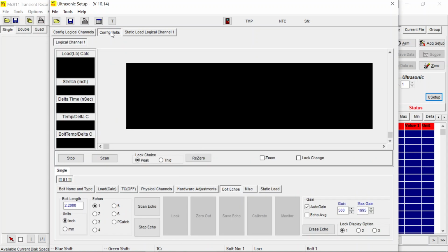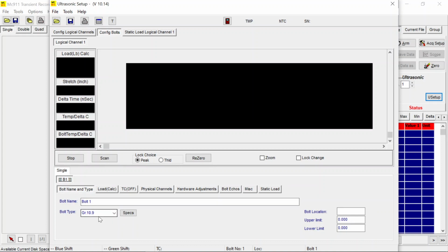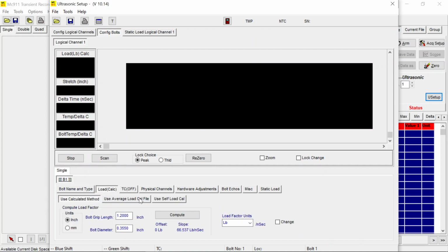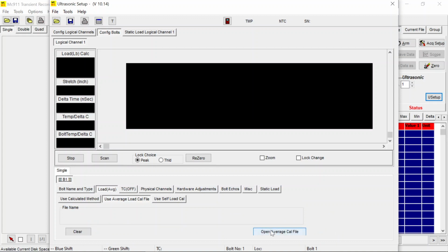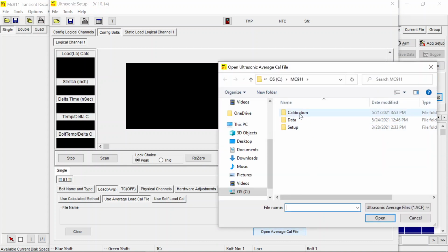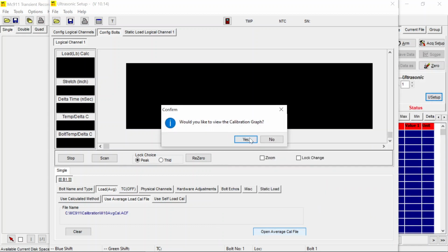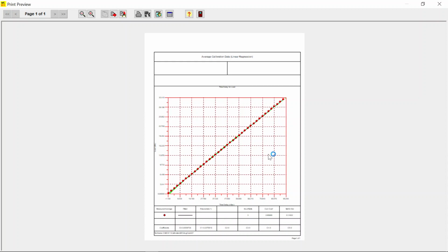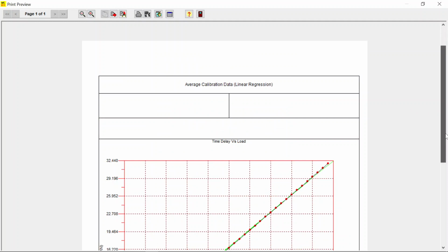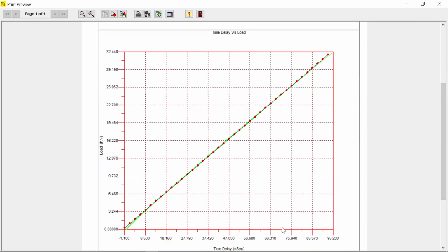So let's go into the config bolt. We have one bolt, 10.9, and our load is based on, let's use the average calibration load that we have generated before. In the previous video, you saw how we generated that calibration file, which was the M10 average cal file. So we're going to use this average calibration file for our load data. Our ultrasonic will be reading time delay, and using this graph, it will show us what the load values are.